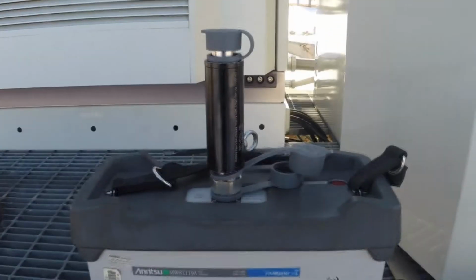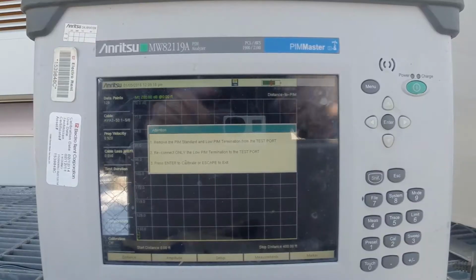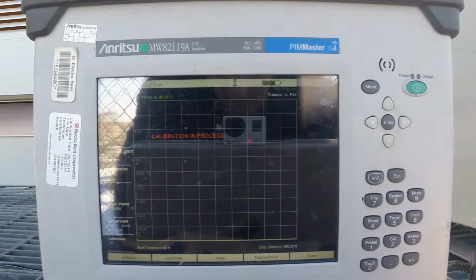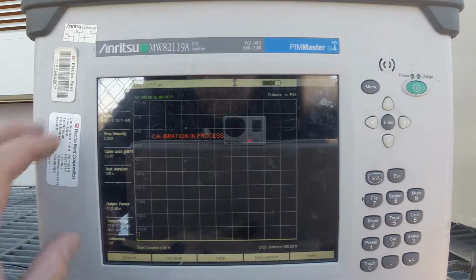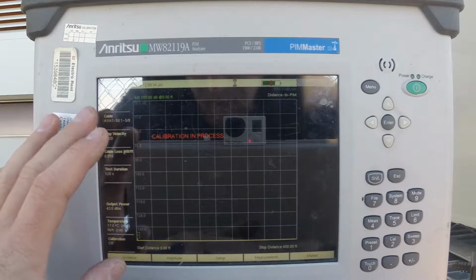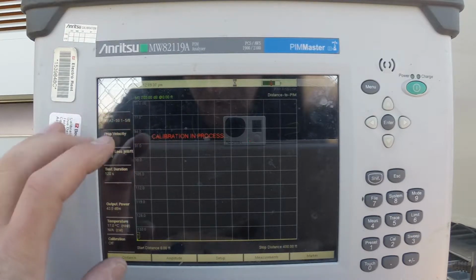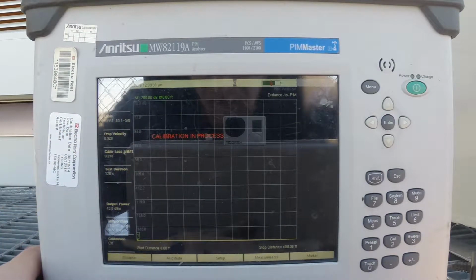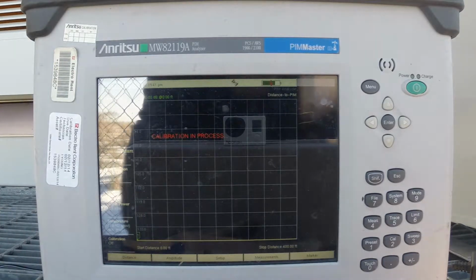Retorque our PIM load. So, again, now we have our PIM load on top of our test unit. We'll hit enter. And this usually takes a couple minutes to do, or a minute or so. And same thing with the distance default on the sweep gear, where you can change your cable. That goes for PIM gear also. We can change our cable. Right now we're on AVA 7, which is 1 5/8 coax. And I'll show you how to set that up in a second here, as soon as it's done.